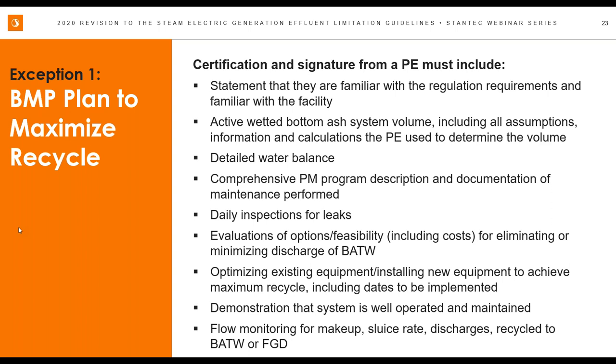Evaluation of options and feasibility for eliminating or minimizing the discharge of bottom ash transport water, optimizing existing equipment, installing new equipment to achieve maximum recycle, including the dates to be implemented, demonstrating that the system is well operated and maintained, and flow monitoring for makeup, sluice rate, discharges, and recycle, actually having flow monitoring in place there. So that may be a modification that's required to systems that have been installed already where those monitors were not put in place.